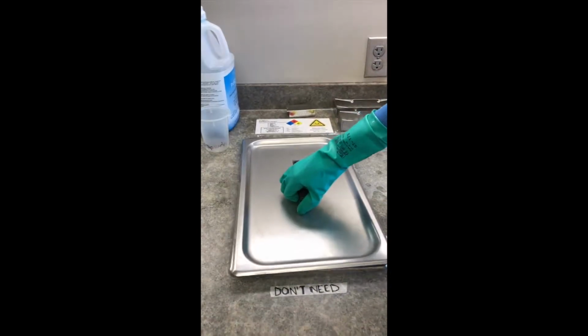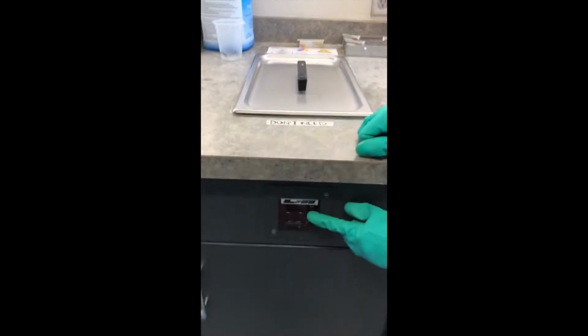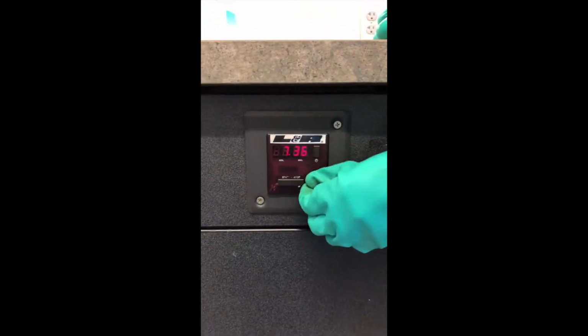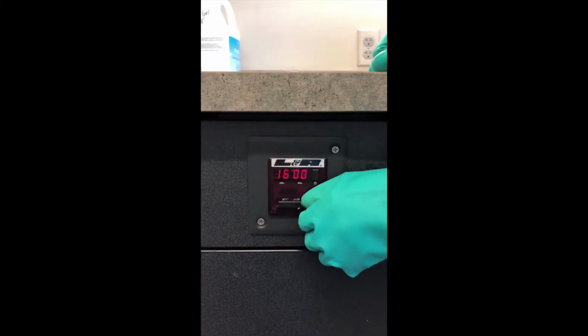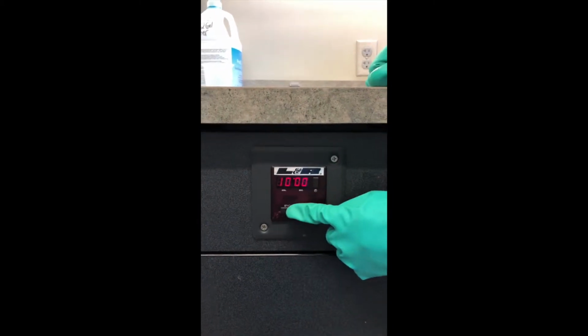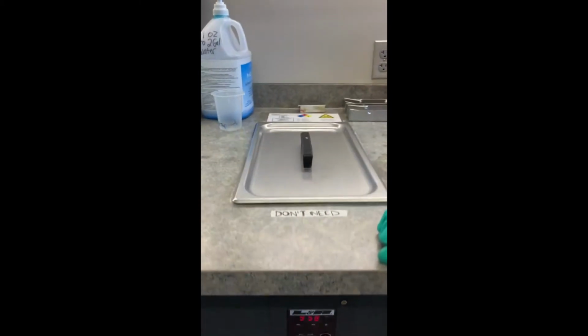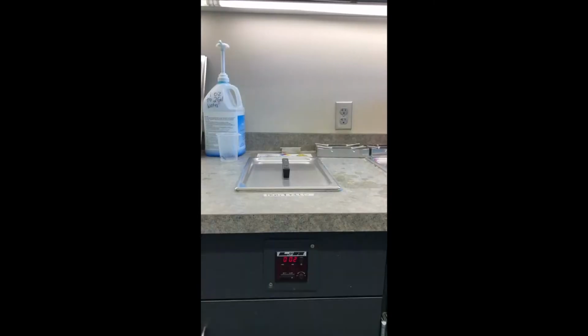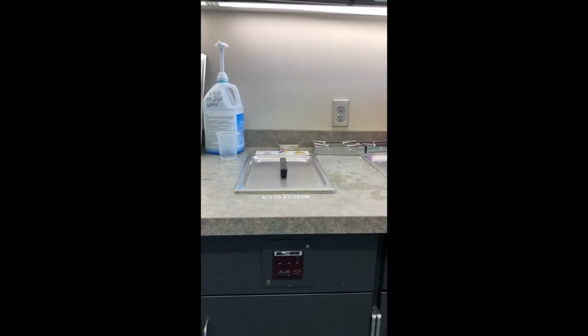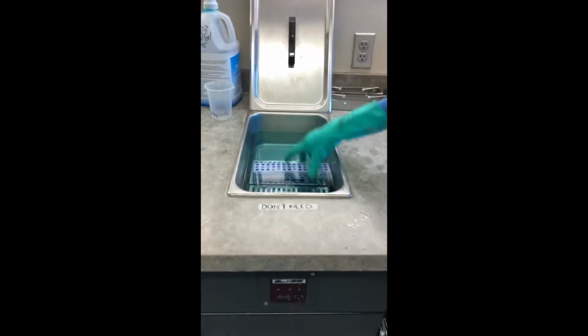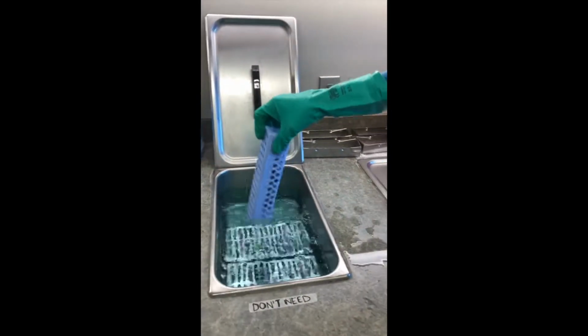Once the ultrasonic bath is filled with the desired instruments, it is time to turn it on. Set bath for 10 minutes for cassettes and 15 minutes for handpieces. Once ultrasonic cycle is complete, lift up the lid and remove the cassette. Shake excess water from cassette.